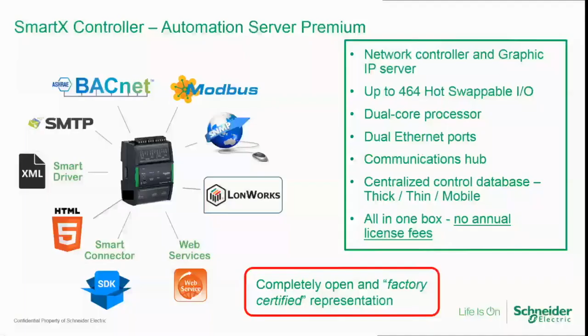I've got a couple slides on hardware to share how we're enabling a lot of these cool things we're talking about. What I'm showing here is our network server. Basically, one way to think about this is it's the interface between your building system and the graphical user interface that facility managers use to see scheduling, trending, and handle alarms. It all goes through this network controller. We run communication buses from the automation server down to all the different field controllers, whether those are VAV boxes, air handling units, chiller plants, whatever.